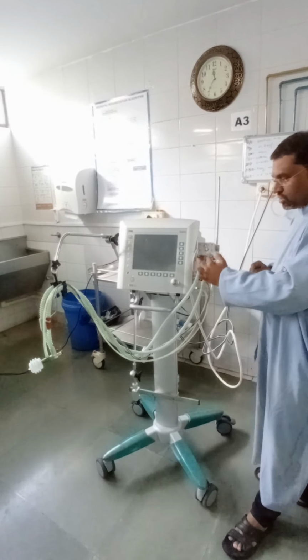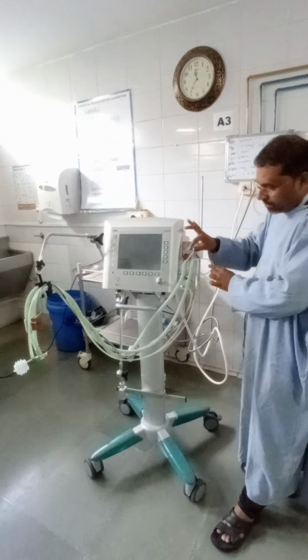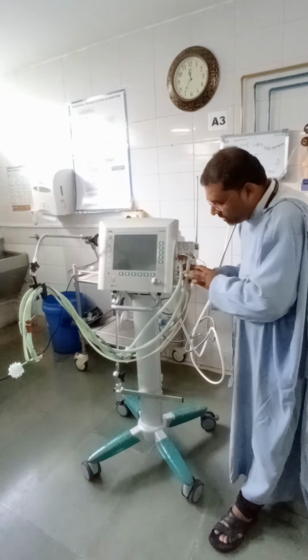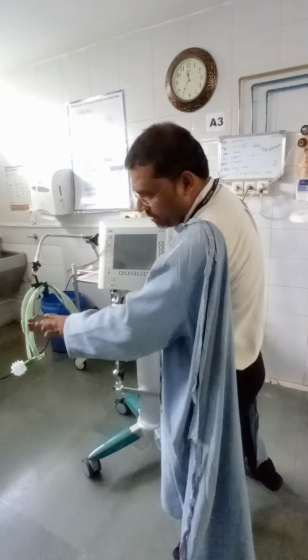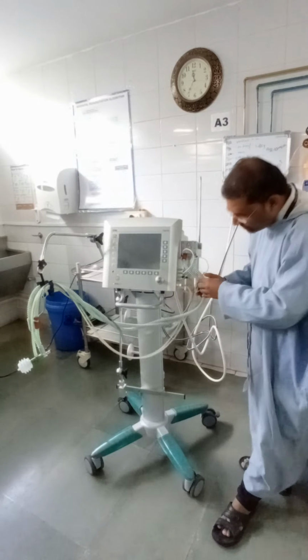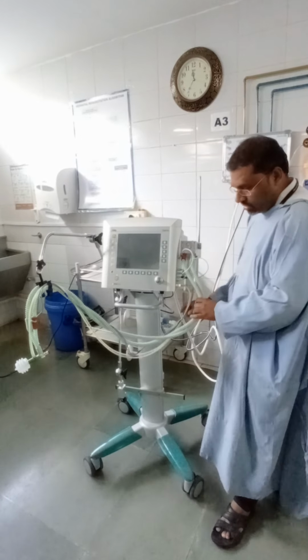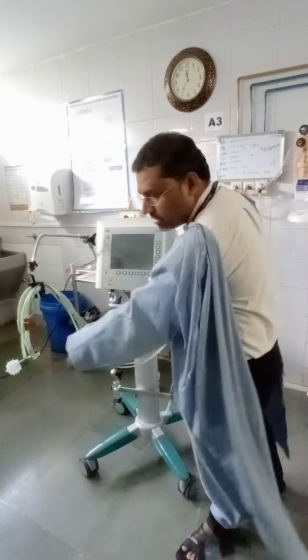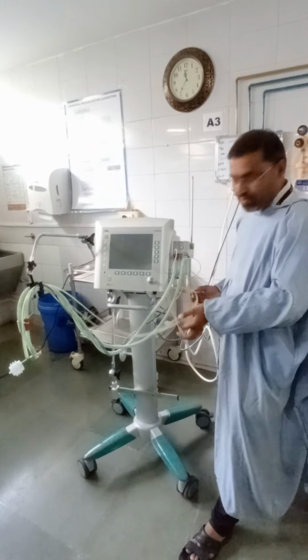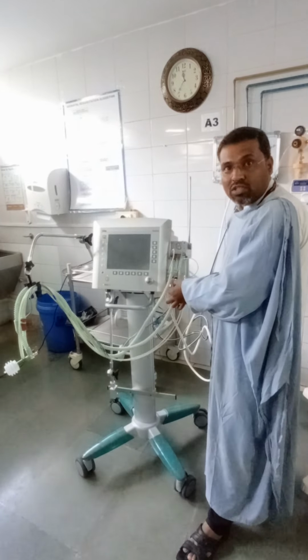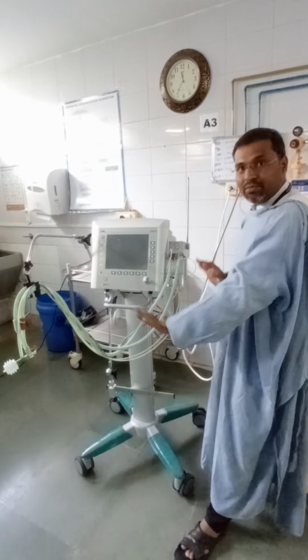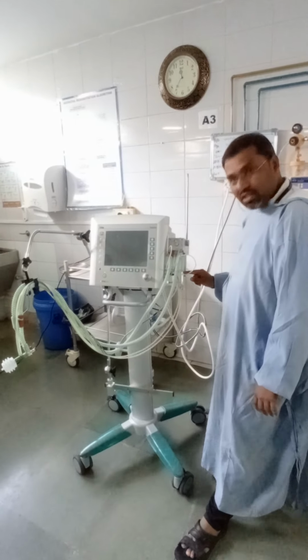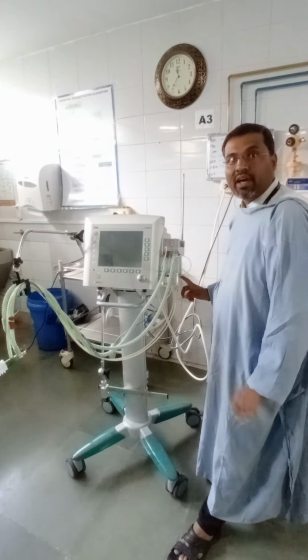Next, for the connection of this tubing, follow the color coding. If your two temperature meter connections are there, you have to connect here, right? You have to connect the temperature sensor here, right? These are the two connections which are coming from the flow sensor. And at the time of connection of this tubing, you have to follow that dot structure, right? So this is your basic arrangement. Before starting, check whether the water is present inside the humidifier or not.